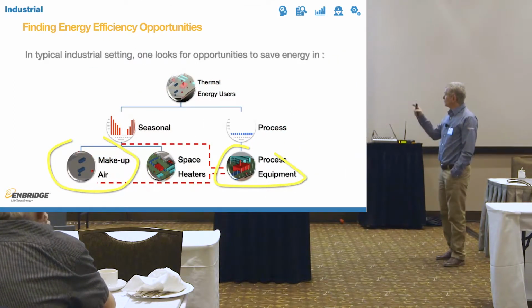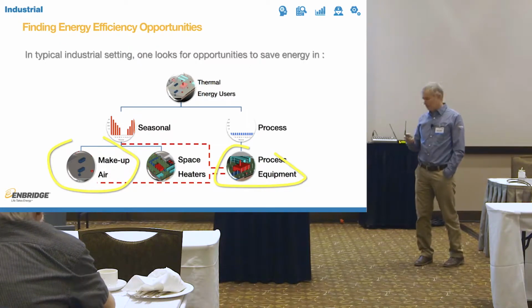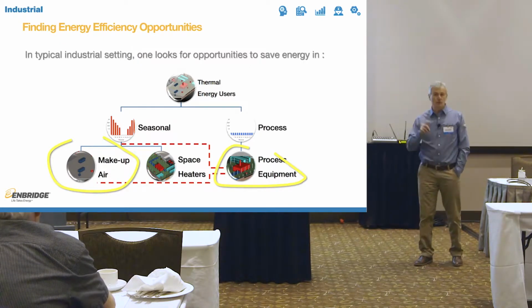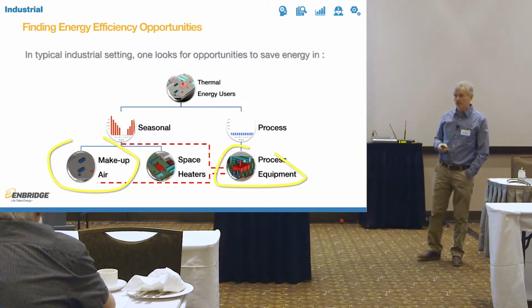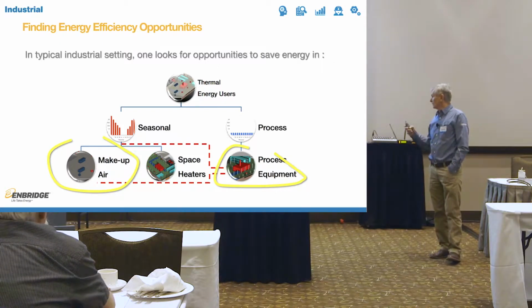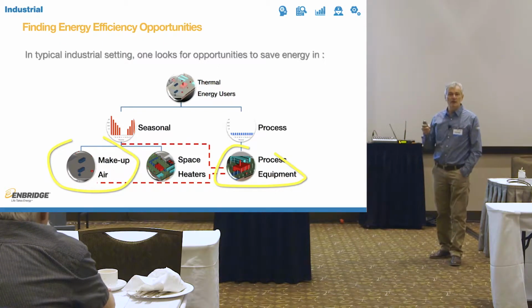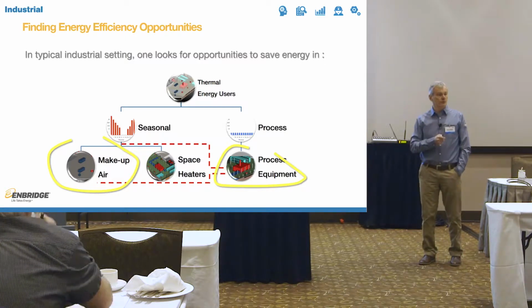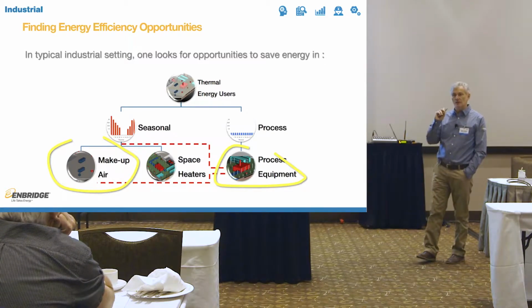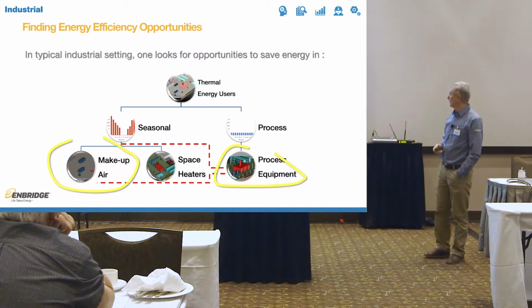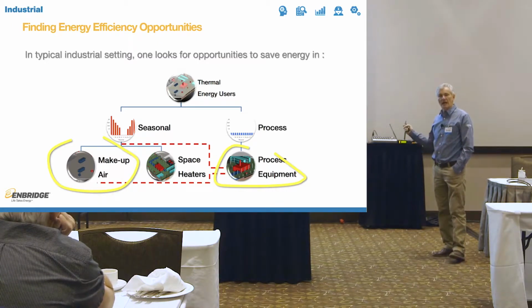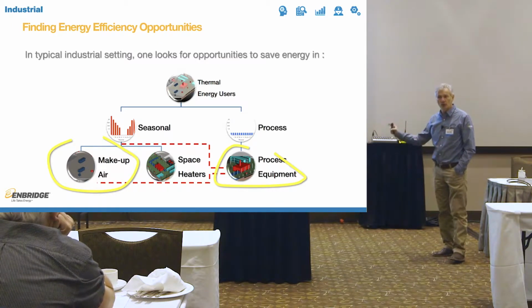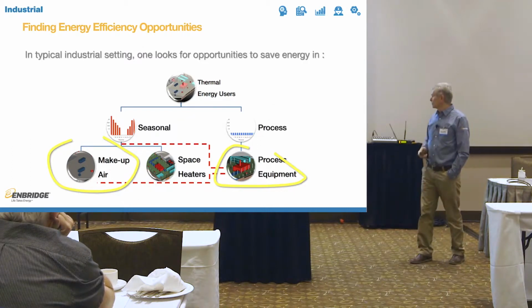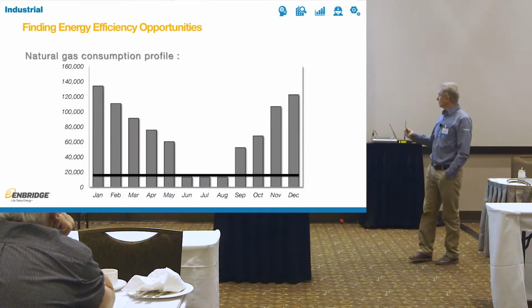So when you think about where to save energy in an industrial facility, not in a facility like this, but in an industrial facility, you really shouldn't be looking at space heaters unless you have exhausted all the opportunities for savings, because that's a minute part of your usage, and you should be focusing on makeup air and your process. And we'll talk about both of those now. So let's start with the makeup air.